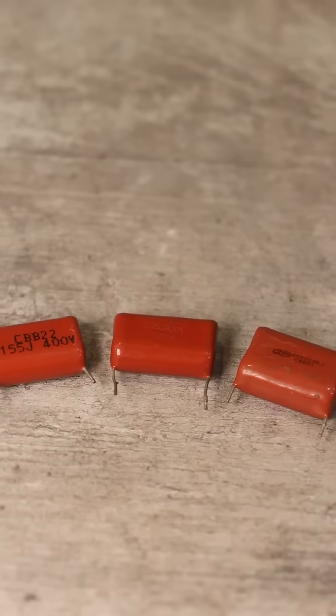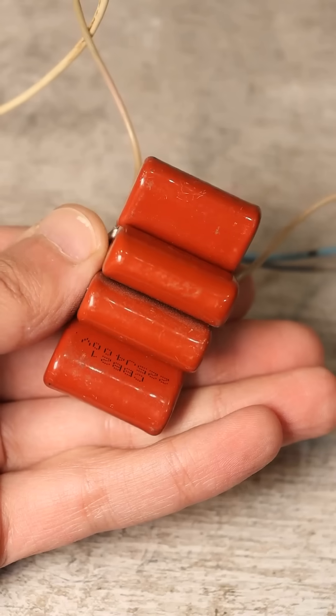When the motor reaches its rated speed in about 3 to 5 seconds, the starting capacitor is disconnected. Its capacity is 2 to 5 times greater than that of the running capacitor.